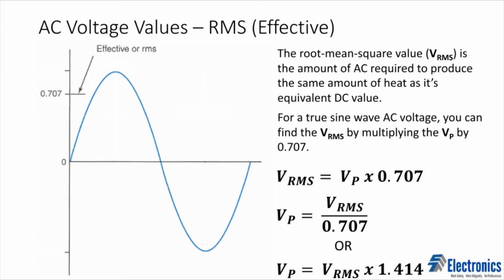Whenever we eventually get back in shop, you're typically going to be looking at Vrms. So when you use your O-scope, especially one of the older analog ones, and you get a sine wave there, you're going to look at what your peak voltage is, and to figure out RMS, you're going to use this formula. Sorry, my fault, because you'll be looking for RMS. So you'll do whatever your peak voltage is times 0.707. Hopefully that makes sense.